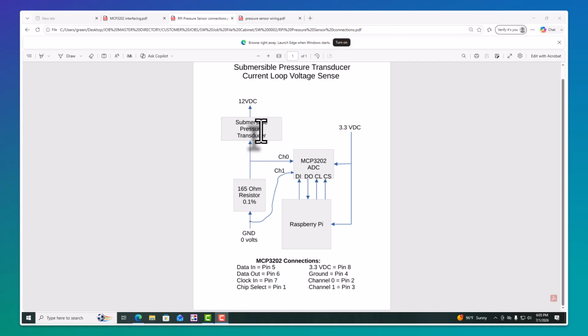When this pressure sensor has no water above it, if it's hanging with no water at the bottom and the tank is empty, it'll output 4 milliamps. So 4 milliamps will flow through this, regardless of the resistor you use. That's important to remember.